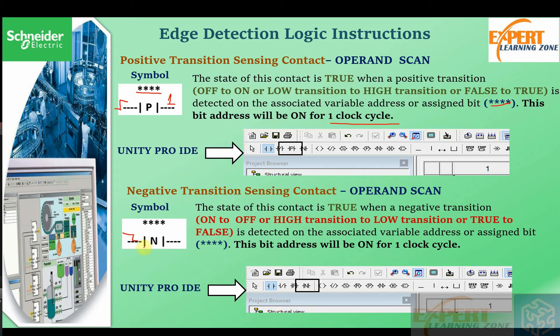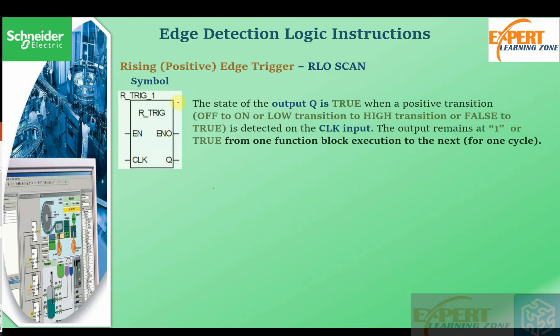For this contact, when we have a transition from the high to the low stage, logic flows from the left side to the right side. The state of this contact is true when a negative transition — on to off, high to low, or true to false — is detected on the associated variable address or assigned bit. When the assigned bit experiences a logic one to logic zero transition, there is a logic one on the right side.